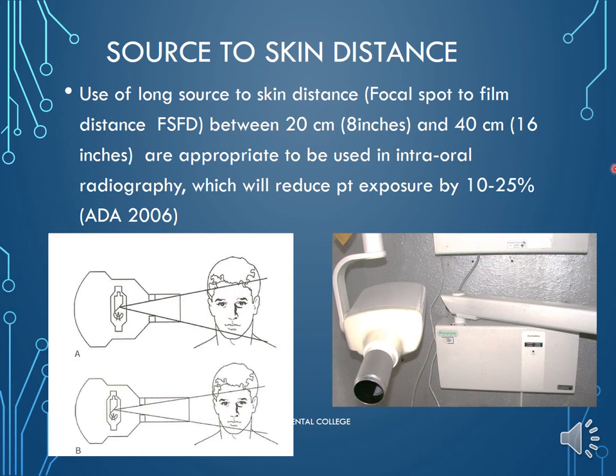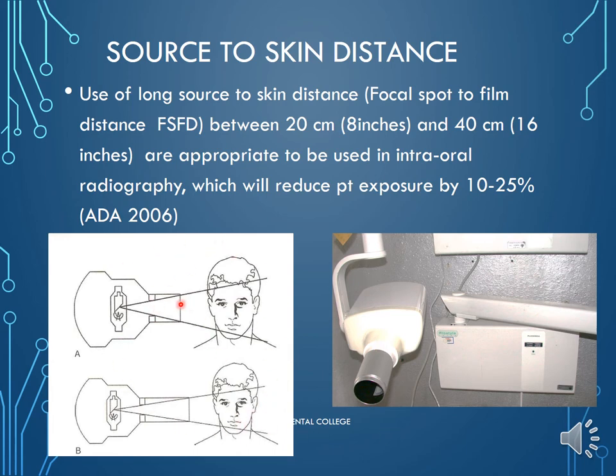Source-to-skin distance refers to the distance from where x-rays are generated to the patient's skin. It is important to use a long source-to-skin distance (also called focal spot to film distance) of between 20 cm and 40 cm (8 to 16 inches). A long cone reduces patient exposure by 10 to 25%. A shorter cone exposes the patient to a larger field of radiation compared to a longer cone, which exposes a smaller area.